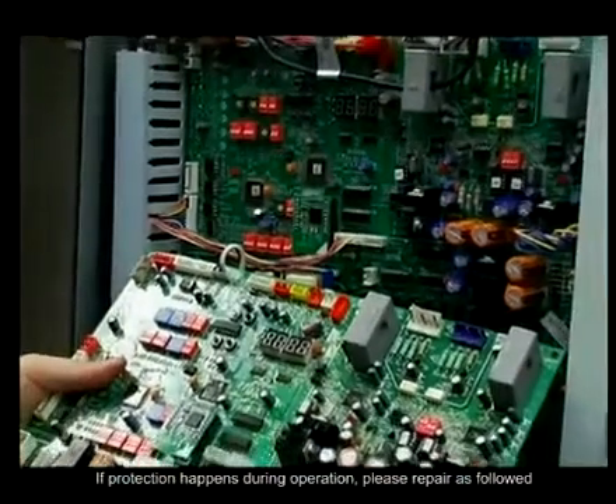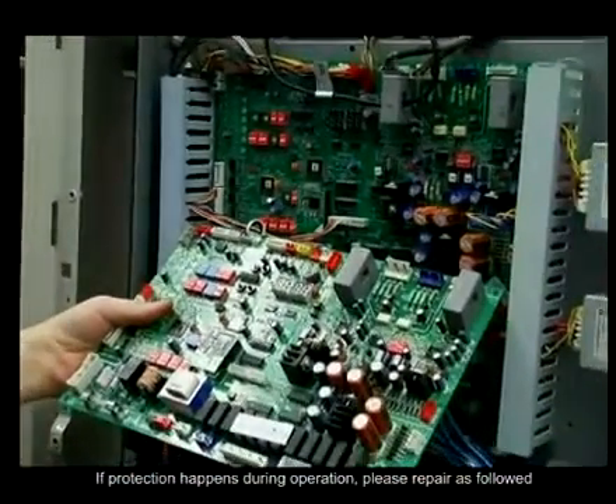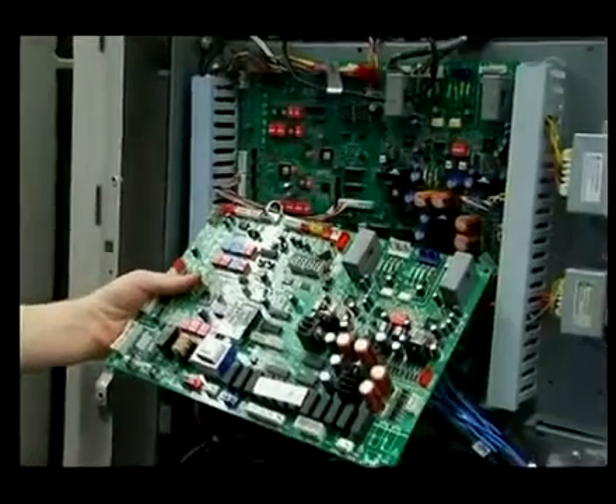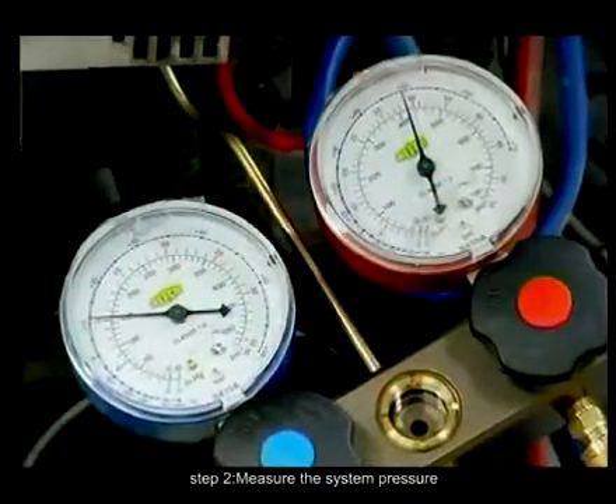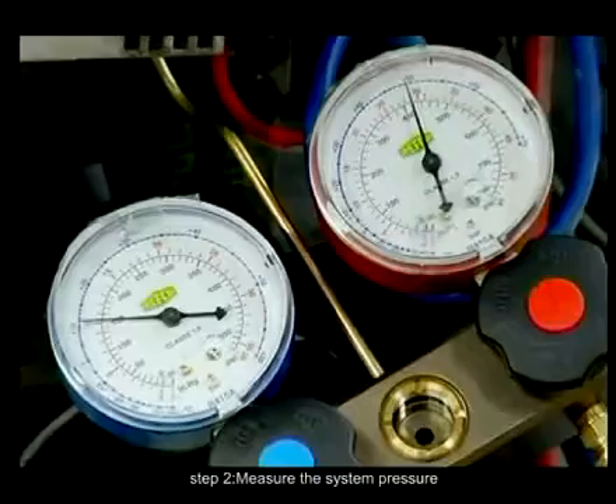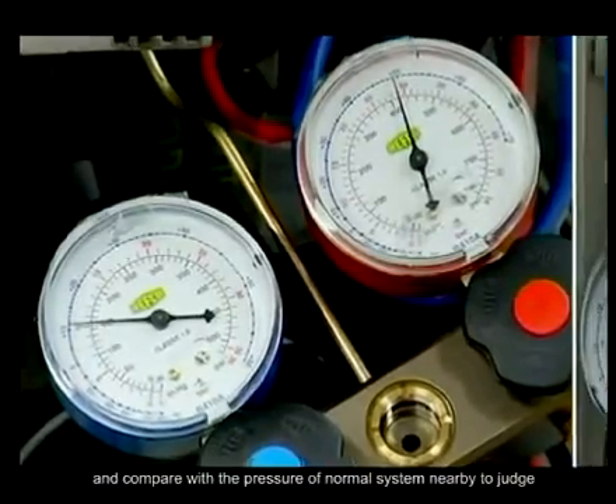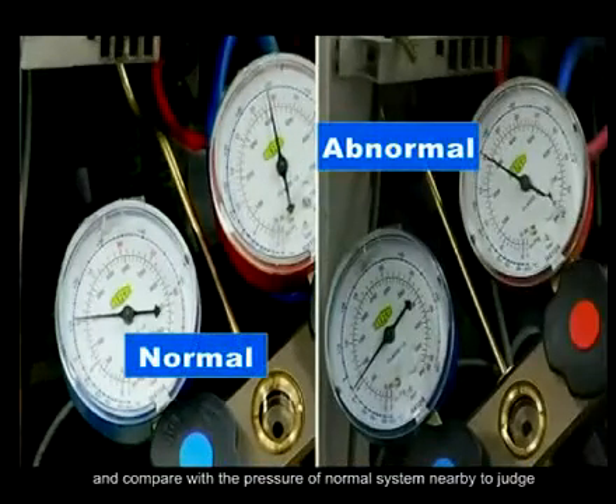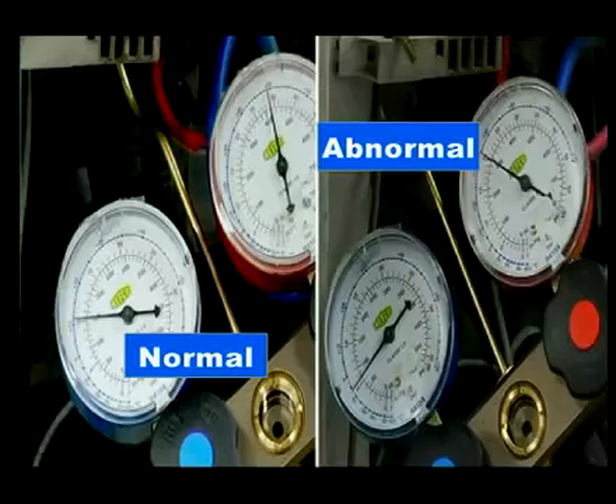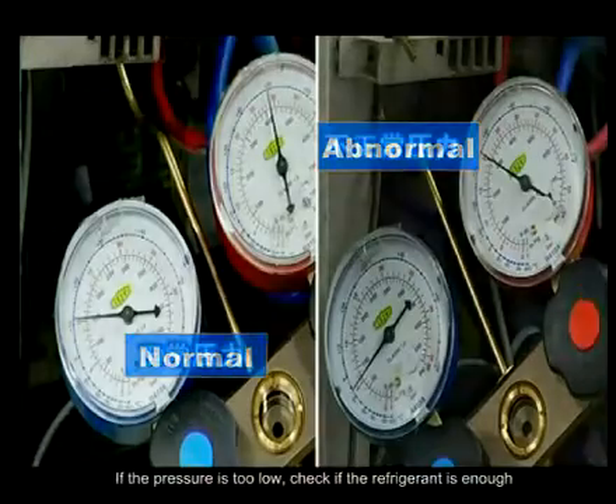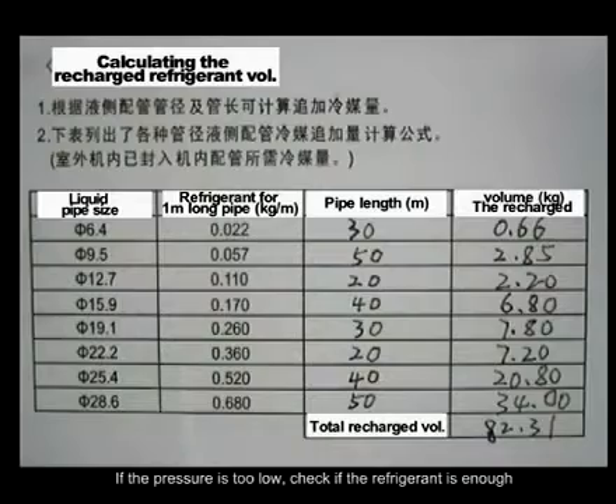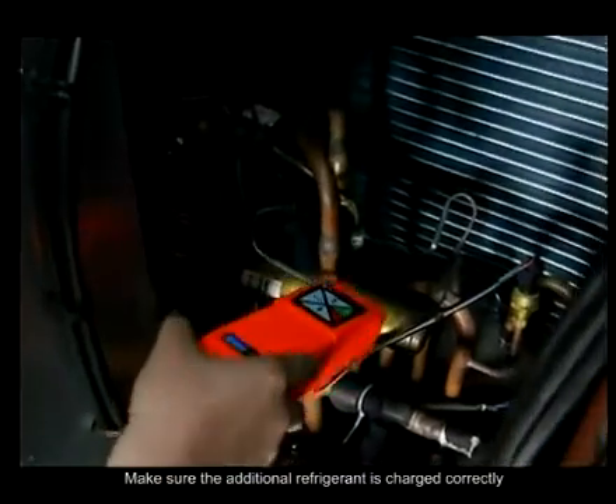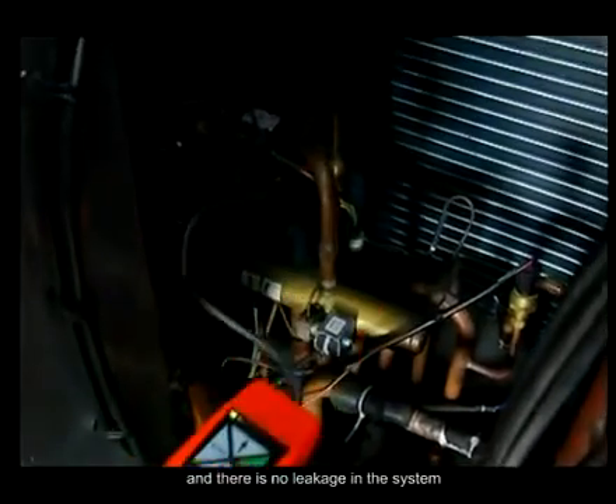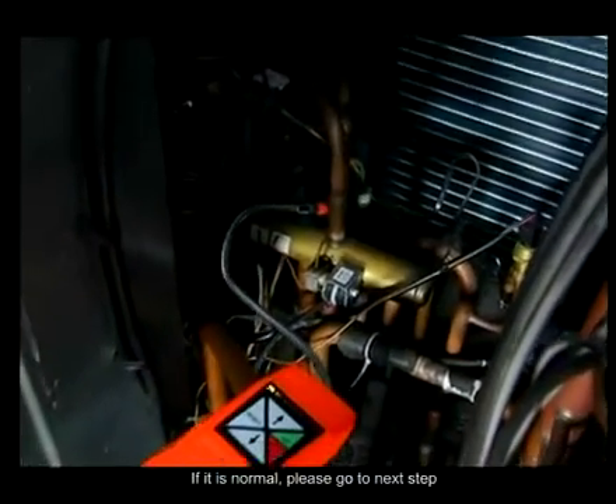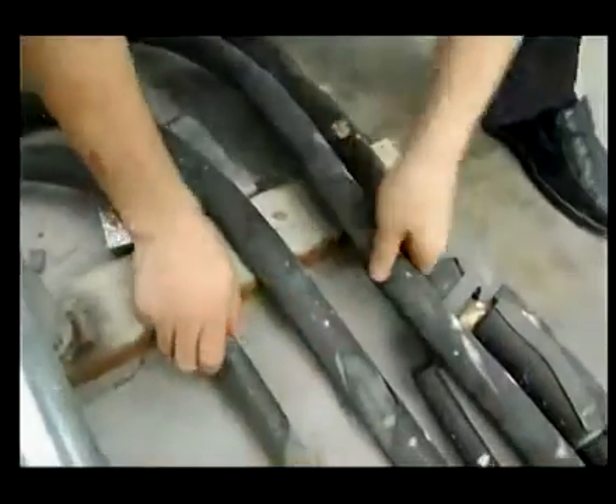If protection happens during operation, please repair as followed. Step 2. Measure the system pressure and compare with the pressure of normal system nearby to judge if the system pressure is too low or not. If the pressure is too low, check if the refrigerant is enough. Make sure the additional refrigerant is charged correctly and there is no leakage in the system. If it is normal, please go to the next step.